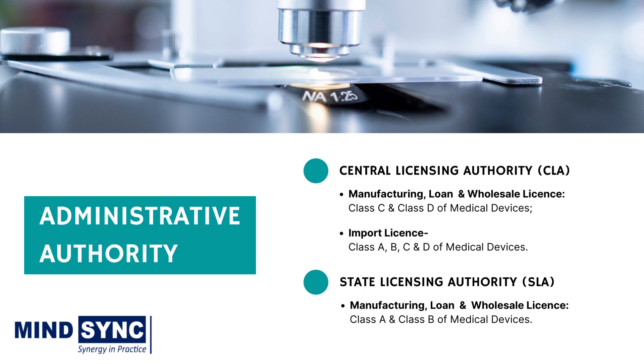Next is the administrative authority. The Medical Devices Rules 2017 recently notified the central licensing authority as the competent authority for providing manufacturing license of Class C and Class D medical devices, and also license for import of all classes of medical devices. Other services include clinical investigation and approval of investigational medical devices, clinical performance evaluation, approval of new in vitro diagnostic medical devices, and coordination with the state licensing authorities. While the state licensing authorities shall be the competent authority for providing manufacturing license of Class A or Class B medical devices, and other services such as sale, stock, exhibit or offer for sale or distribution of medical devices of all classes.